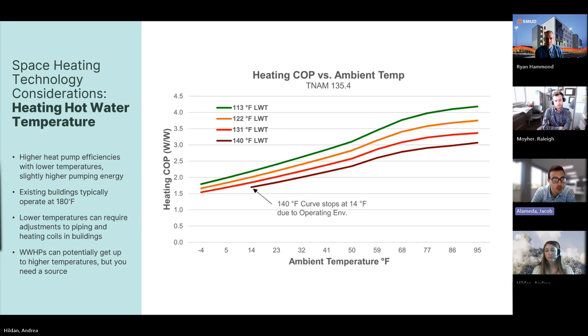Two, air-to-water heat pump equipment can technically give you 140-degree supply temperatures, but most manufacturers prefer you to design around 130 degrees just to avoid pushing their equipment as hard as it can go. In new builds, new heating coils can be selected around these lower temperatures without a problem. But on retrofit projects with existing coils and piping designed around 180-degree supply temperatures, these lower supply temperatures can become a problem. However, from what we're seeing, existing heating systems in older buildings tend to be oversized a lot of the time and can actually handle lower supply temperatures some of the time.